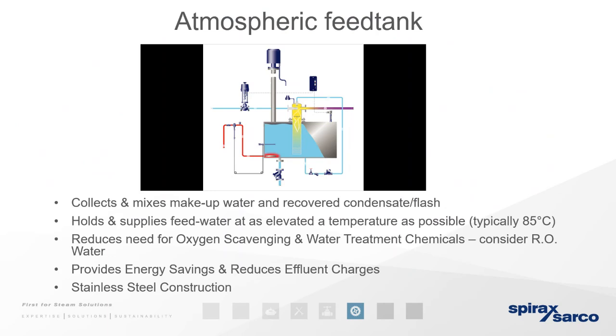So as you can see here, atmospheric feed tanks, if we talk about those, we have deaerators, which are quite generic, as Bosch can offer as well. The way they work, as Alvin's already covered, is to preheat the water to create as much efficiency in the energy in the water that's being supplied to the boiler. As you can see here, the elevated temperature is possible. A normal feed tank tends to be around 85 degrees. The higher you can raise that, up to about 103, 105 degrees, the more it reduces the oxygen, and therefore reduces the need for as much chemicals. You will still need some.